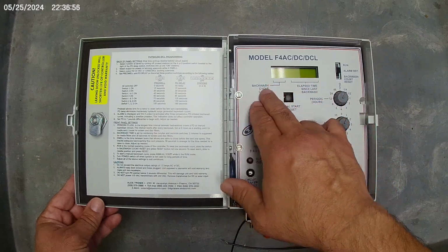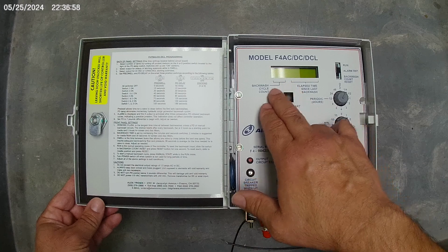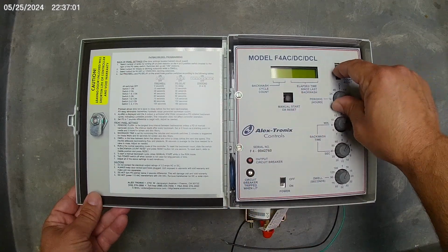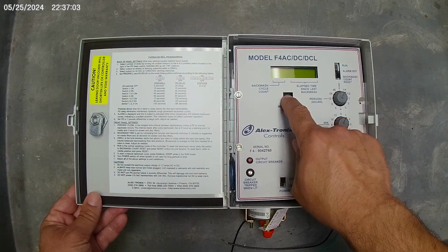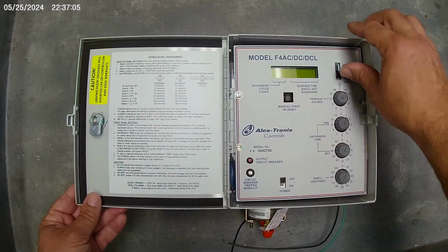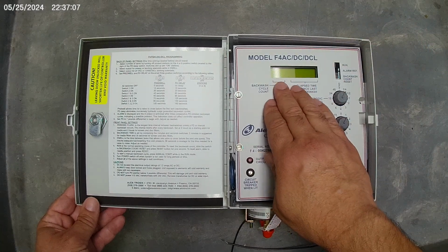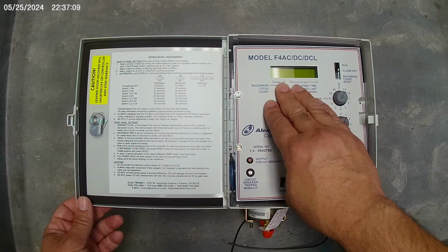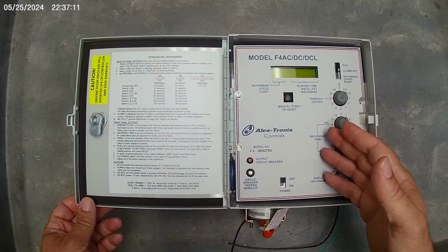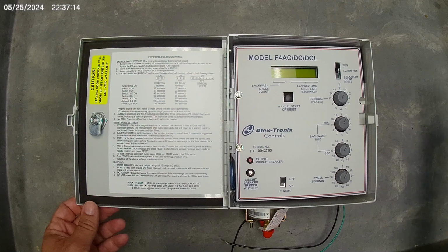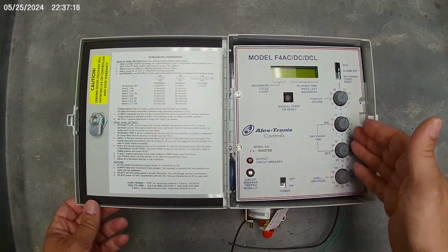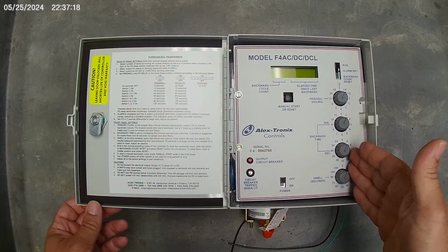Additionally, if we want to reset our displayed backwash cycle count, we move the switch to the bottom again and hold it down for a few seconds, and that'll clear that value. Some people like to do that every time they service the controller or are near it, so they can come back and get an idea of how often it's flushing, if they've got a problem with too much effluent getting into the filters, or if they need to adjust their backflush times.